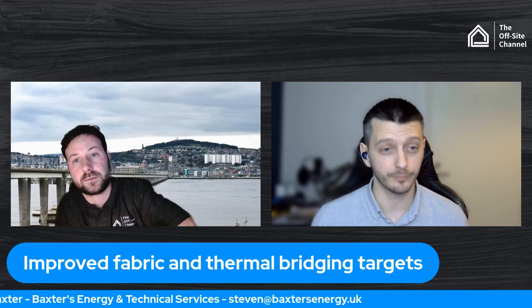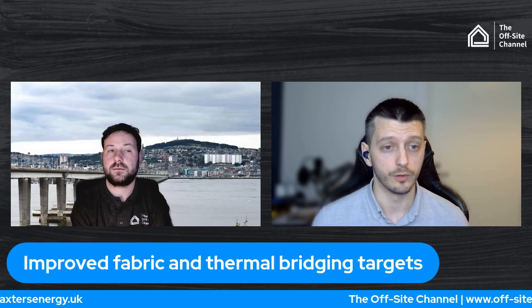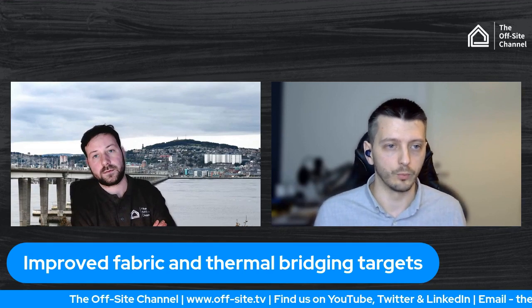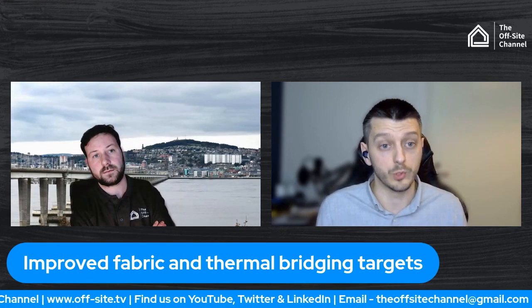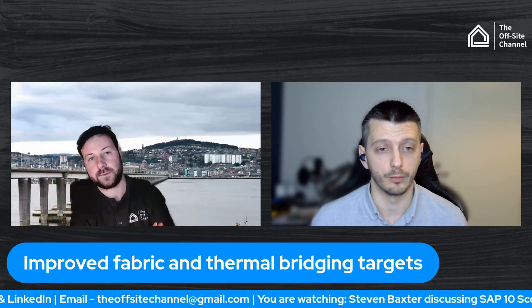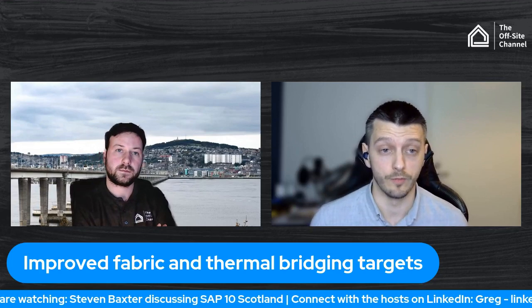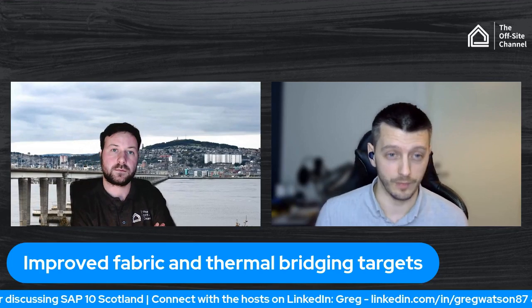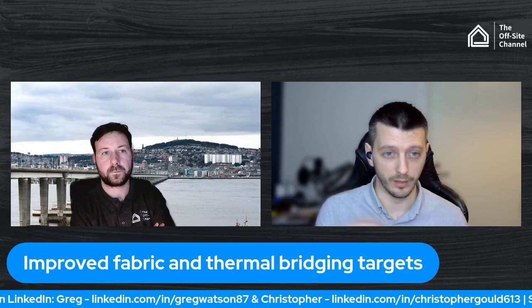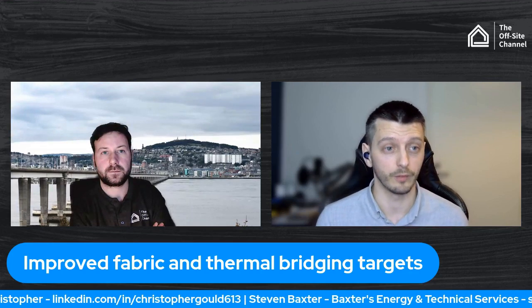Yeah. Second half of that question as well, I guess. We've talked about the improved fabric. There's also the improved thermal bridging targets. Previously, the notional dwelling that we're assessing our houses against was set at 0.08 for the thermal bridging level. But the new notional dwelling is set to 0.05. Now, looking at previous projects I've done with calculated thermal bridging values, that's in the ballpark of where you would be if you have lots of calculated bridging values.